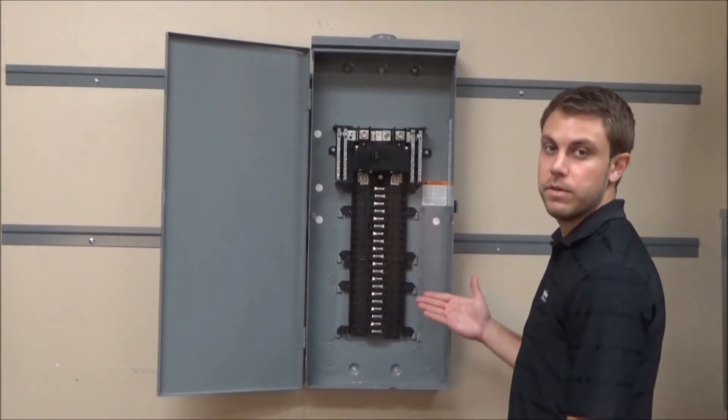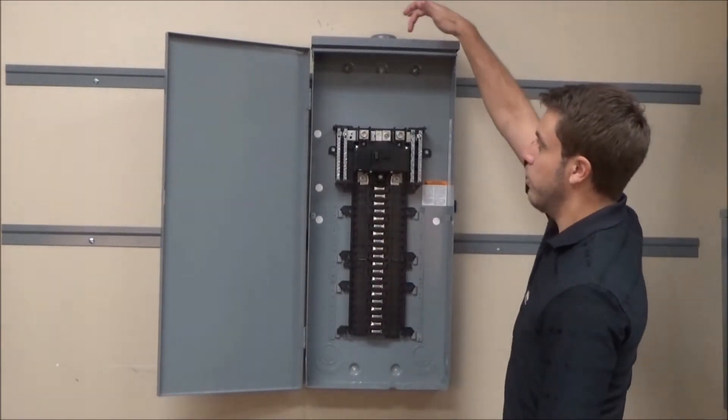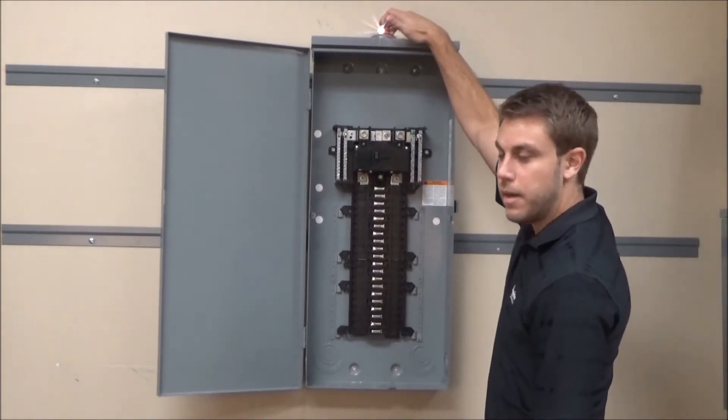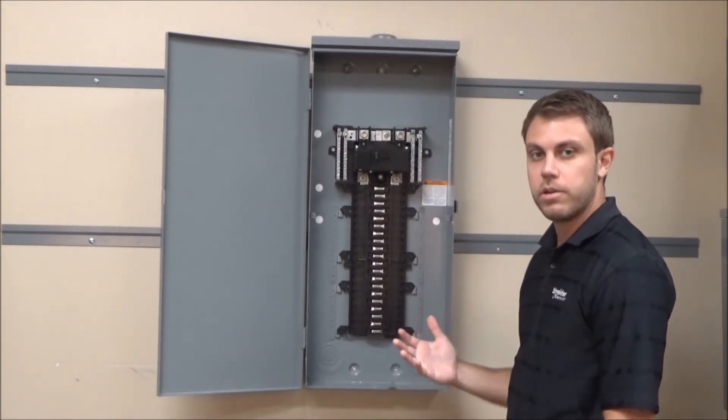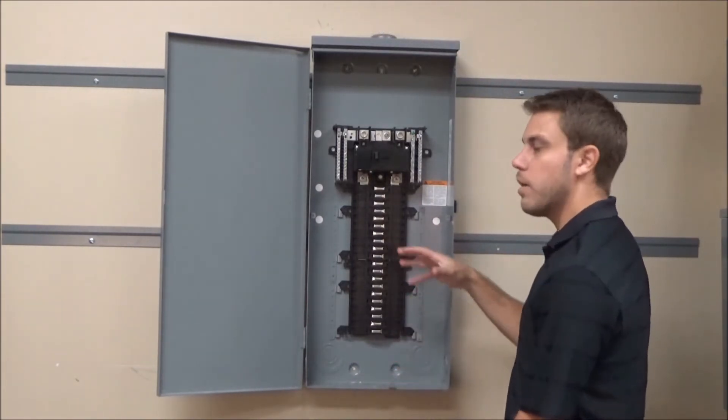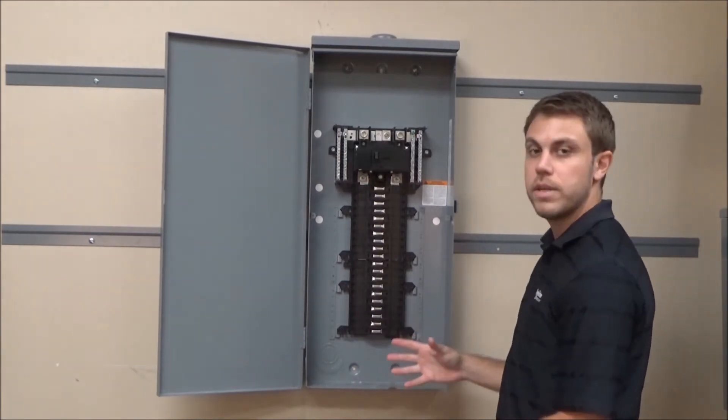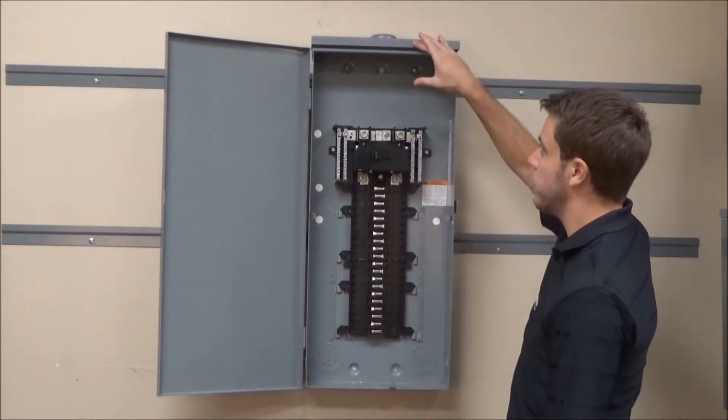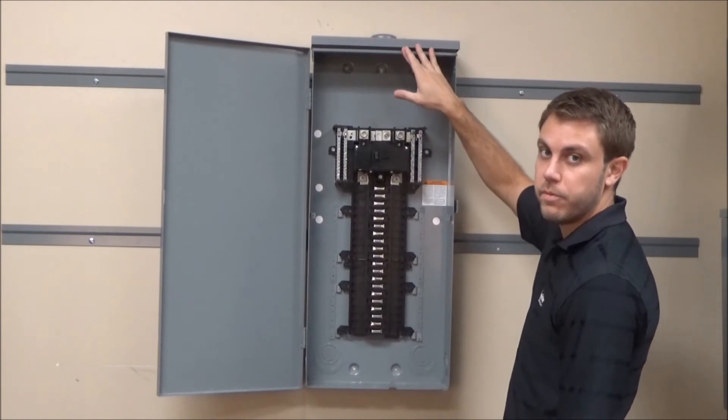With our NEMA 3R load center they're normally set up for overhead feed with the hub opening at the top, but if you do want to underground feed the load center, you do not rotate it like a normal NEMA 1 load center due to the NEMA 3R drip hood that's at the top to prevent water getting in.